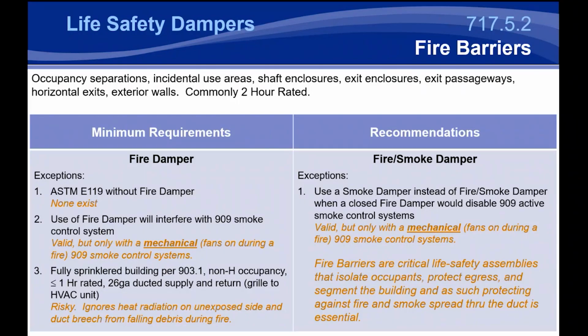Now, what we'll also start talking about with this presentation is different exceptions for removing the need for, say, fire dampers or smoke dampers, and where that is throughout the code, why it's risky, and what we recommend. Now, a lot of these exceptions are going to be common across multiple barriers. If it is an exception for one, it may apply to multiple barriers. I'm not going to go over them at each different barrier. I may reiterate some differences between different barriers and some additional requirements, say for shaft walls, but for the most part, a lot of these exceptions are going to be common throughout this presentation.